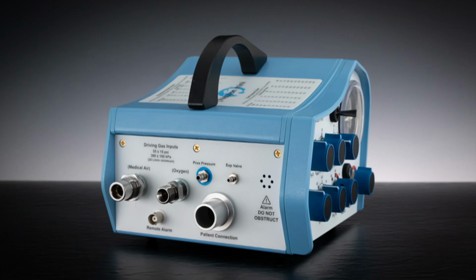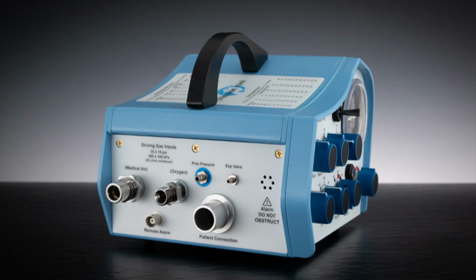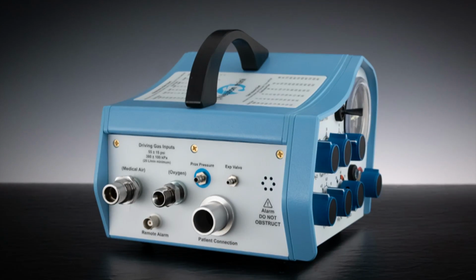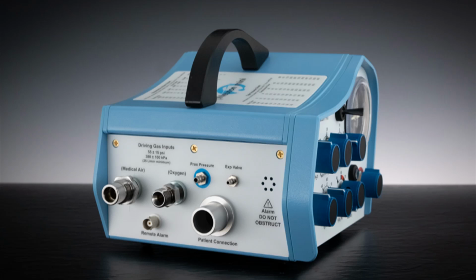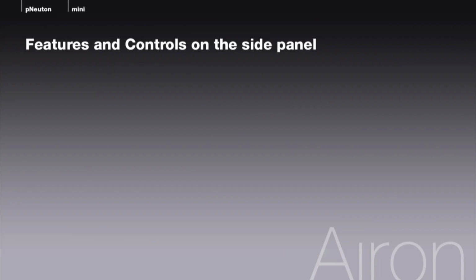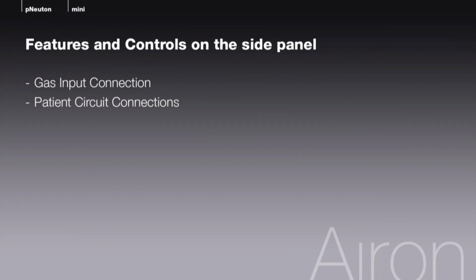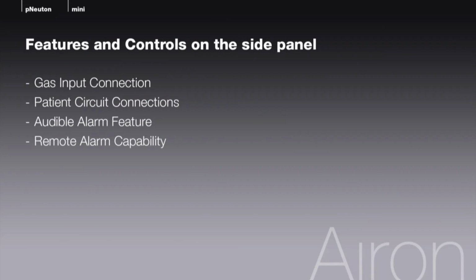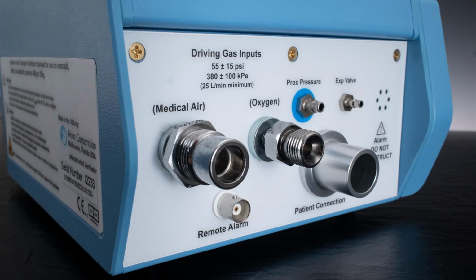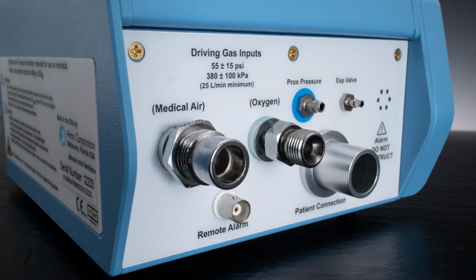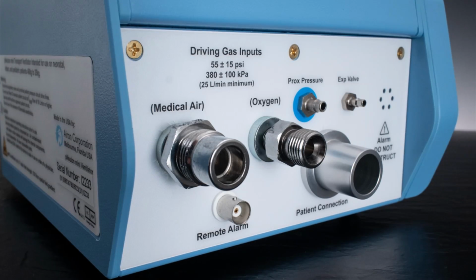You'll note that with the Newton Mini, all the connections for patient circuit and blended gas are found on the left side panel of the device. Let's take a look at the gas input connection, patient circuit connections, audible alarm feature, and the remote alarm capability. Driving gas input connections. The first item we will look at on the side panel is the driving gas input connection. Keep in mind the Newton Mini does not require electricity or batteries.